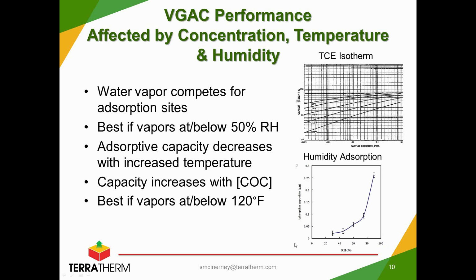In the lower curve, you can see the humidity adsorption curve here: at or about 50% relative humidity, the adsorption of water into a carbon bed really accelerates. So an industry rule of thumb is you want to be at or below 50% relative humidity. When you're conditioning your gas stream and designing a system to do that, that's really your target. And again, looking at the isotherm curves here, you can see that at higher temperatures you get much lower adsorptive capacity, and that improves as you reduce the temperature. We focus on TerraTherm being at or below 120 degrees Fahrenheit as often as we can to really beef up the adsorptive capacity of the carbon and reduce the amount of waste that we have to deal with off-site.